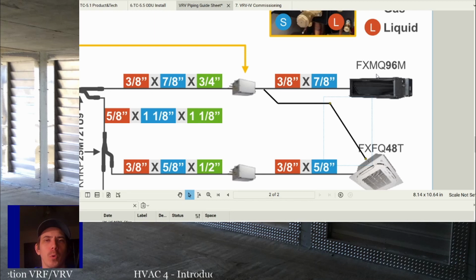For those of you who are more familiar with commercial, you'll know that most of your interior rooms are generally cooling only. They don't need very much heat. And most of your outer areas could need heat or cool depending on the situation. Plus, along the perimeter of the building, those units generally need more heating or cooling, whereas the indoor section might not. How I like to put it, and this may not be the right way to say it, is that those two areas have different load diversity. Those two areas have different needs.